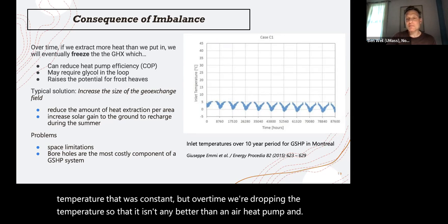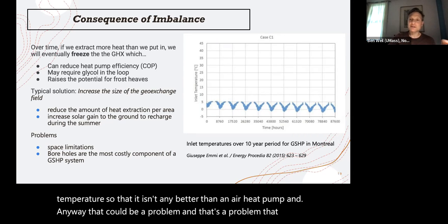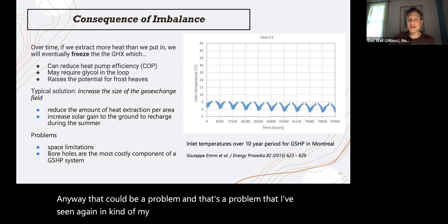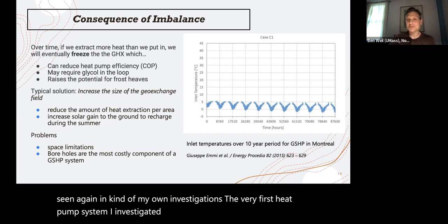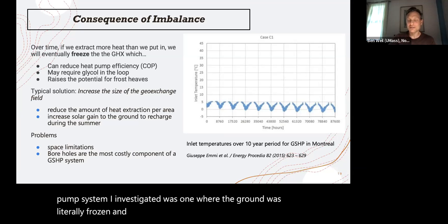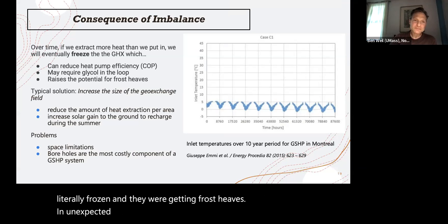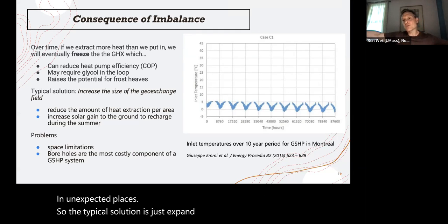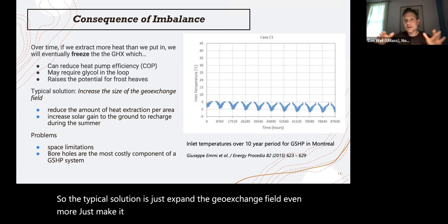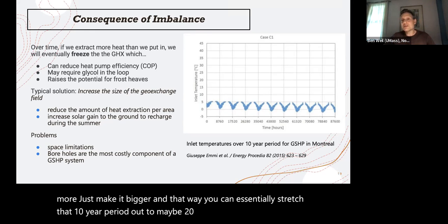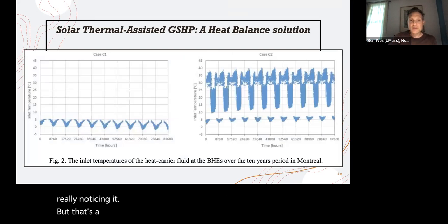Anyway, that can be a problem, and that's a problem that I've seen in my own investigations. Actually, the very first heat pump system I investigated was one where the ground was literally frozen and they were actually getting frost heaves in unexpected places. So the typical solution is just to expand the geoexchange field even more, make it bigger. And that way you can essentially stretch that 10-year period out to maybe 20, maybe 30 years without really noticing it. But that's a big oversize.